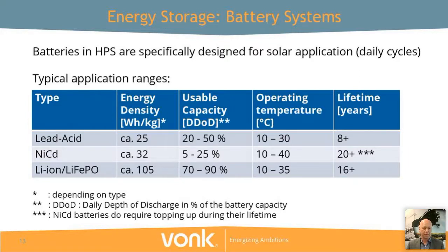Of course price, which is not in this table, is important. Recyclability is also a very important factor—whether it's allowed or not. In many occasions, offshore lithium-ion is still not allowed. So in this table you can see the different properties and typical application ranges for the three most commonly used battery types: lead acid, nickel cadmium, and lithium-ion. In this case, the lithium ferrophosphate—it should be a 4 behind the PO—but it's the lithium ferro battery type.